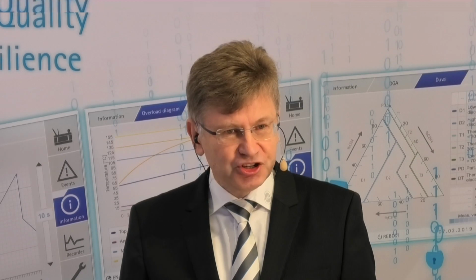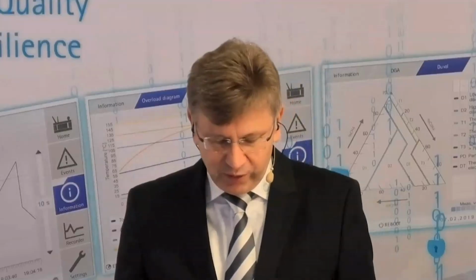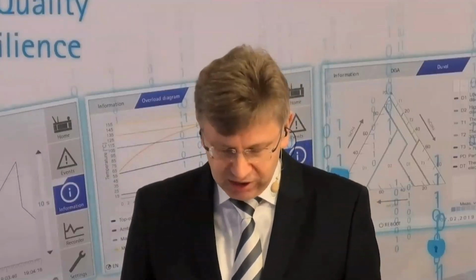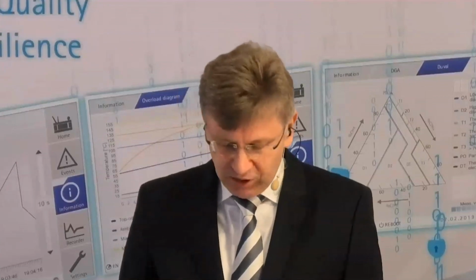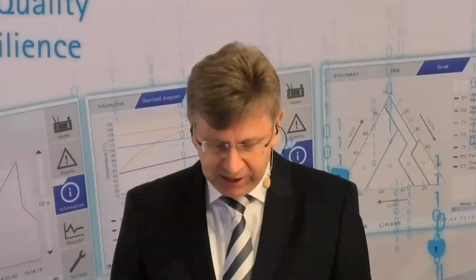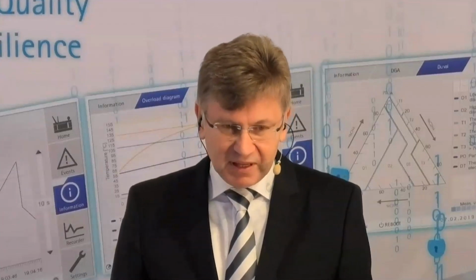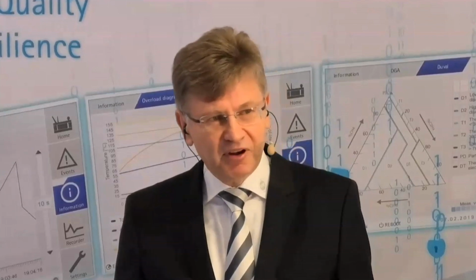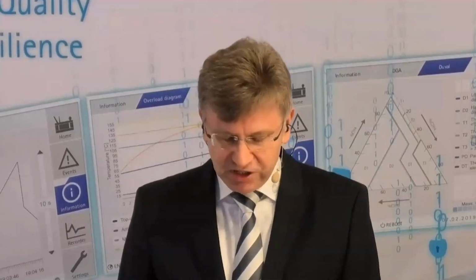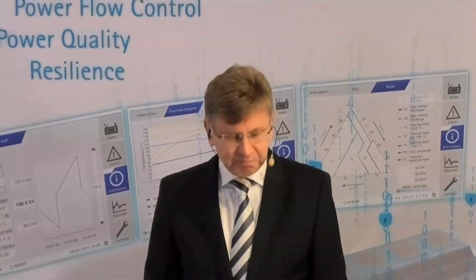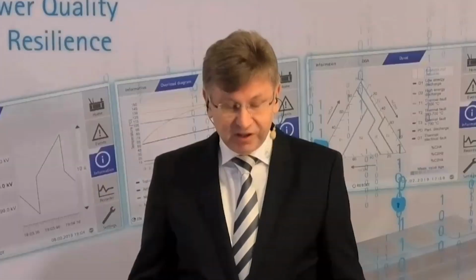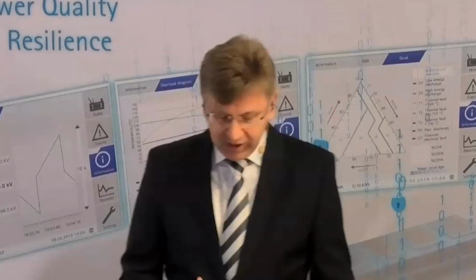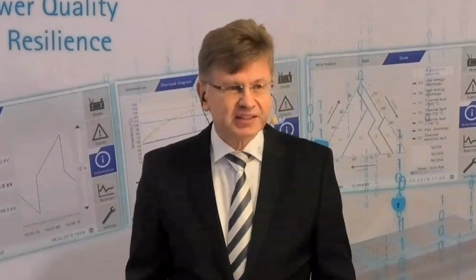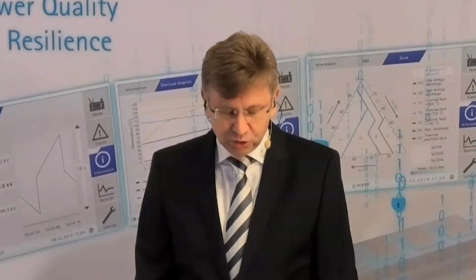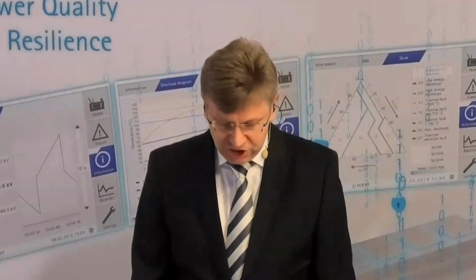This somehow changed now with the new forms of generation, with wind farms, with solar, the variable power generation, the variable directions of loads, of power, the different impedances of lines. All these change it from a steady power flow into a floating bi-directional power flow. Transmission utilities have actually less direct influence in order to control these changed conditions.